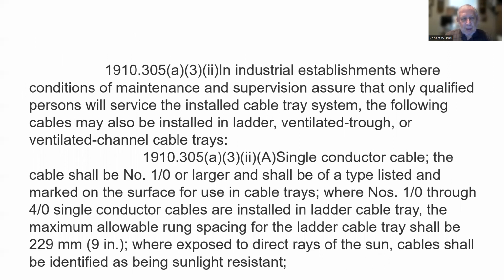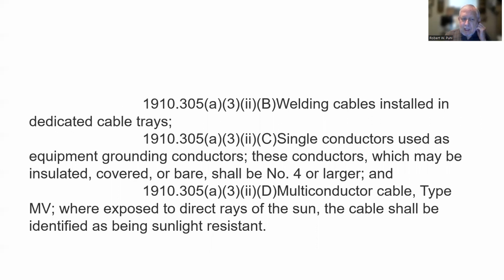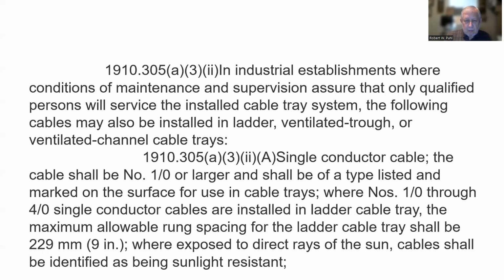In industrial establishments where conditions of maintenance and supervision assure that only qualified persons will service the installed cable tray system, the following cables may also be installed in ladder, ventilated trough, or ventilated channel cable trays. And I'm not going to read all those, but that would be like in a separate room somewhere. And OK Foods had a lot of those, where they were locked, and you had to have a key to get in, so they weren't open to anybody. Welding cables installed in dedicated cable trays. These are welding cables. Single conductors used as equipment grounding conductors. Oh, wait a minute.